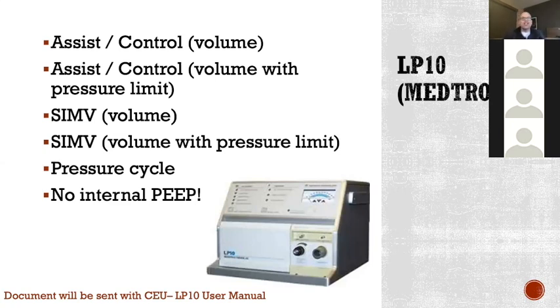What we do is just like on an ambu bag, where we want to give PEEP with an ambu bag, we put a PEEP valve on it, right? That's just a little valve that we dial up to how much PEEP we want, and we stick it on that spot on the ambu bag. Well, on these ventilators, we would stick a PEEP valve on the exhalation circuit. There's a spot for it. There's instructions in the box. If you get one from the strategic stockpile, it shows you where to put that PEEP valve, and then you would dial the PEEP on that. So it's not a setting on the ventilator. Instead, it's the piece of plastic that we're putting on.